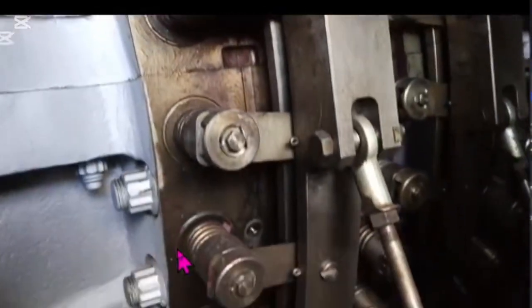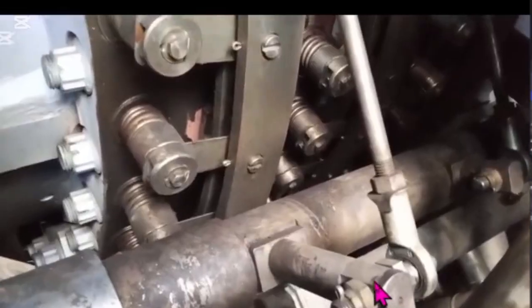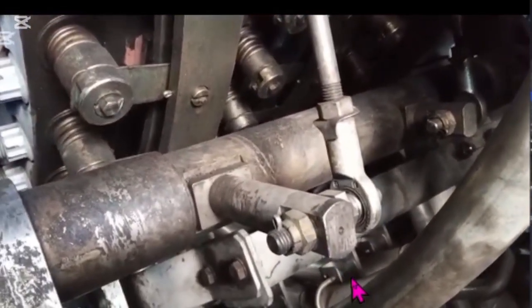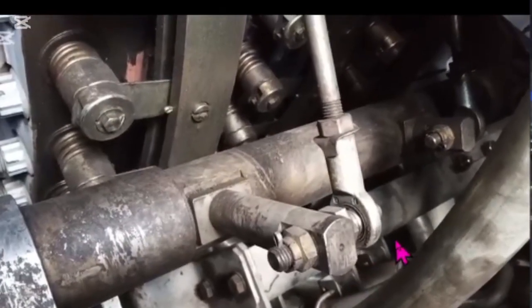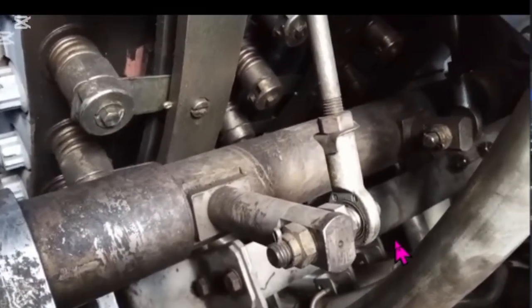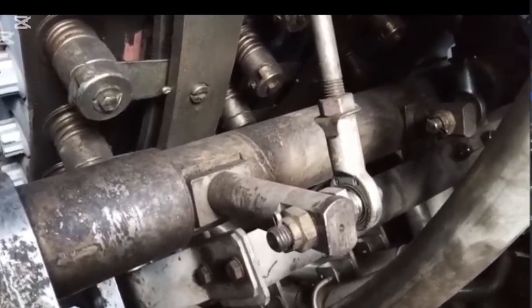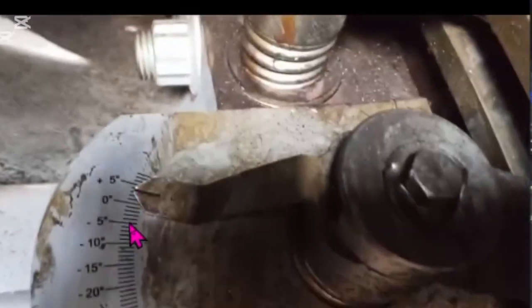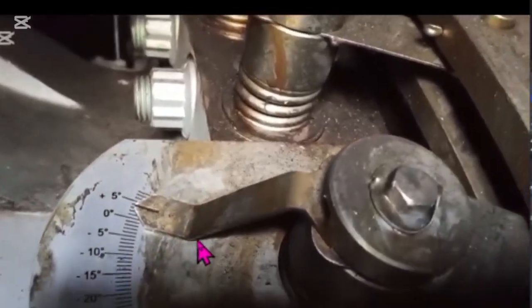This is at 75%, likely -11 position. Now we applied 100% open and we follow what happened. Now we apply 100 from our DCS and here we will follow what the output value is. Now it is +4. It means +4 is showing.